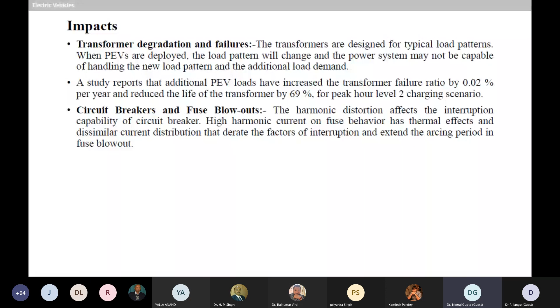Harmonic distortion affects the interruption capability of a circuit breaker. High harmonic current on the fuse has thermal effects and dissimilar current distribution that derate the interruption factors and extend the arcing period of the fuse blowout.